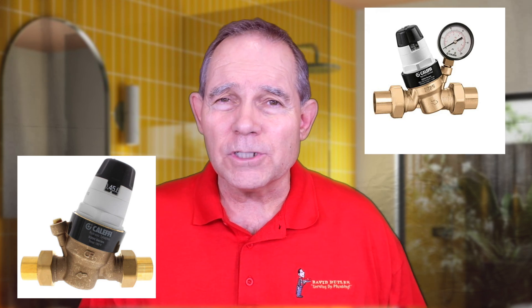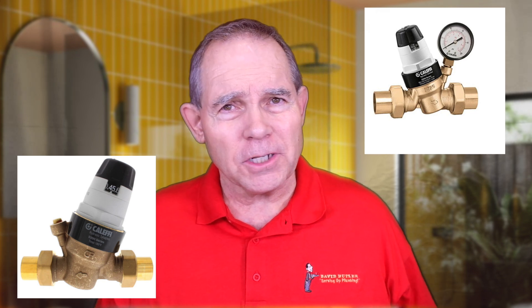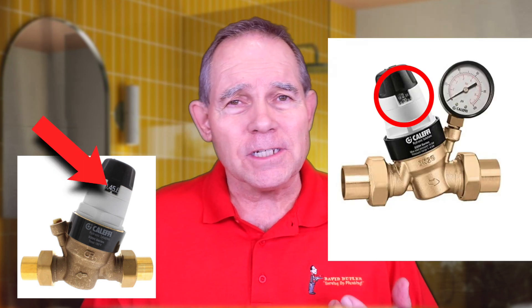The reason we use Caleffi is it's very easy to adjust — even a homeowner can do it themselves if they wanted to. Some PRVs, you can't tell what pressure you've adjusted it to without actually having a pressure gauge on your faucet. Others, as you can see with the Caleffi, you can actually dial it in to an exact pressure and it's usually very close to that pressure. Along with different manufacturers, there are also a lot of different ways you can install a PRV. They can be installed inside the house if your water shutoff is in the house, in the ground at the front of the house, or at the meter, which some cities require.